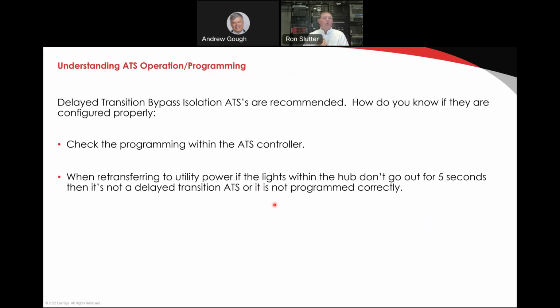All right, so delayed transition is something that has to be programmed. Okay, so I've been in sites. How do we know when the ATS is delayed or not? Well, a really simple way to know is typically the lights in your facility will tell you a lot about the transition of your utility services. So when we move from utility or we lose utility at your facility, what happens to the lights? They usually go off, right? Until that generator starts and the ATS transfers to emergency. So it could be 30 seconds, a minute, depending on what you have in your facility before the lights come back on. It's a pretty good indicator that you've lost utility power.